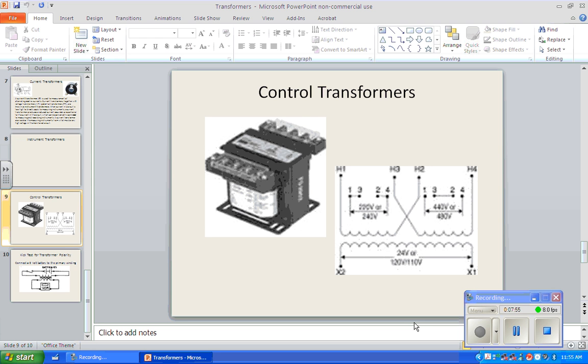And control transformers - we've talked about control transformers in our theory class. If you haven't heard that lecture, I would look that up and listen to it. The thing you need to know is it's designed to operate on two different primary voltages, depending on how you hook it up, and always put out 120 volts. That's what a control transformer does. A lot of across-the-line starters have a control transformer because it's one of the safer ways to supply the control circuit power.